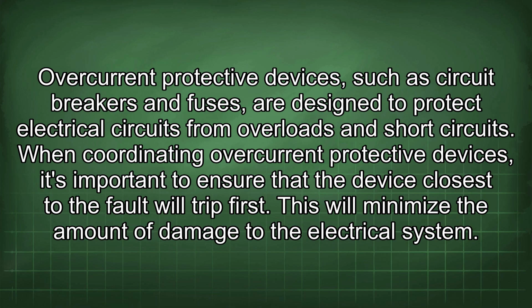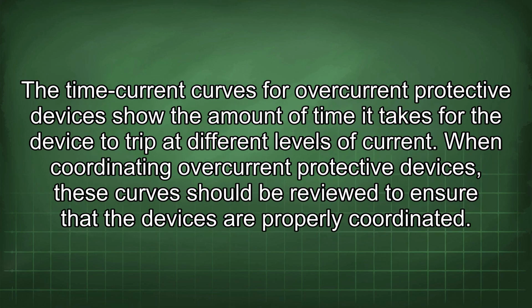When coordinating overcurrent protective devices, it's important to ensure that the device closest to the fault will trip first. This will minimize the amount of damage to the electrical system. The time current curves for overcurrent protective devices show the amount of time it takes for the device to trip at different levels of current. When coordinating overcurrent protective devices, these curves should be reviewed to ensure that the devices are properly coordinated.